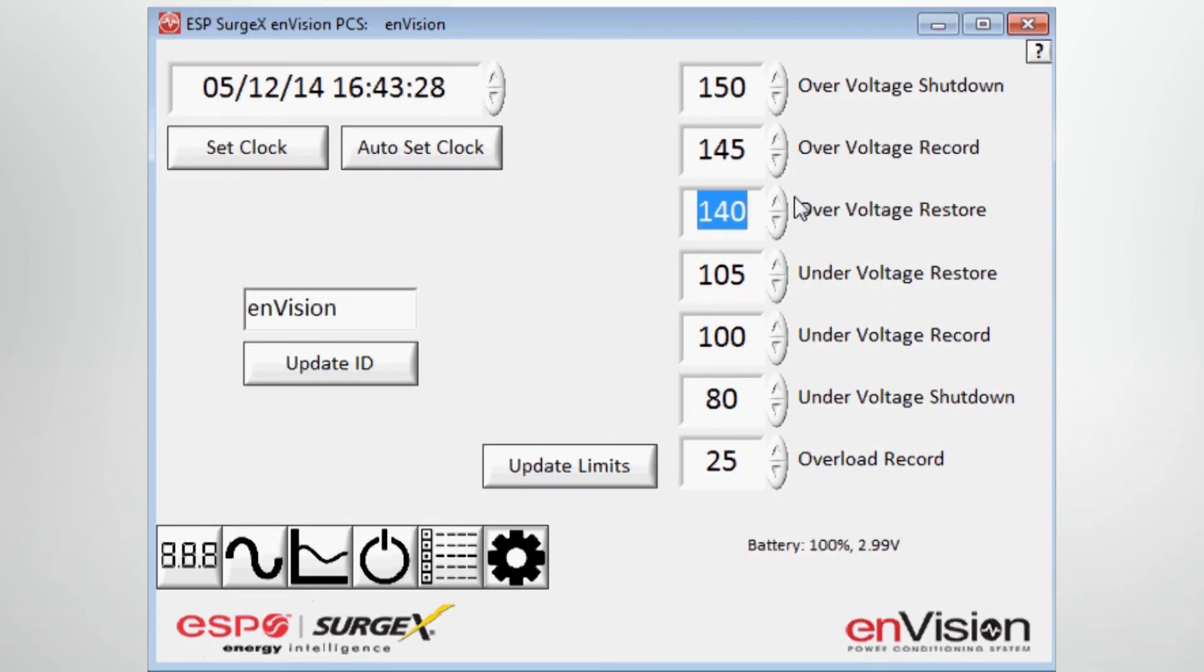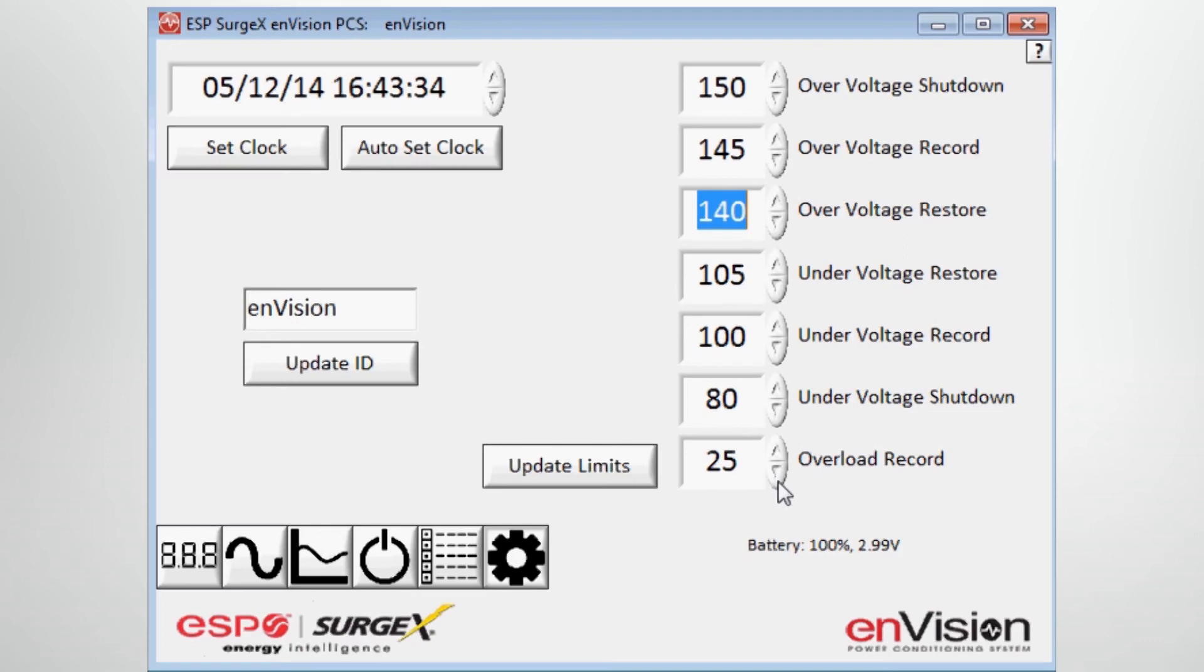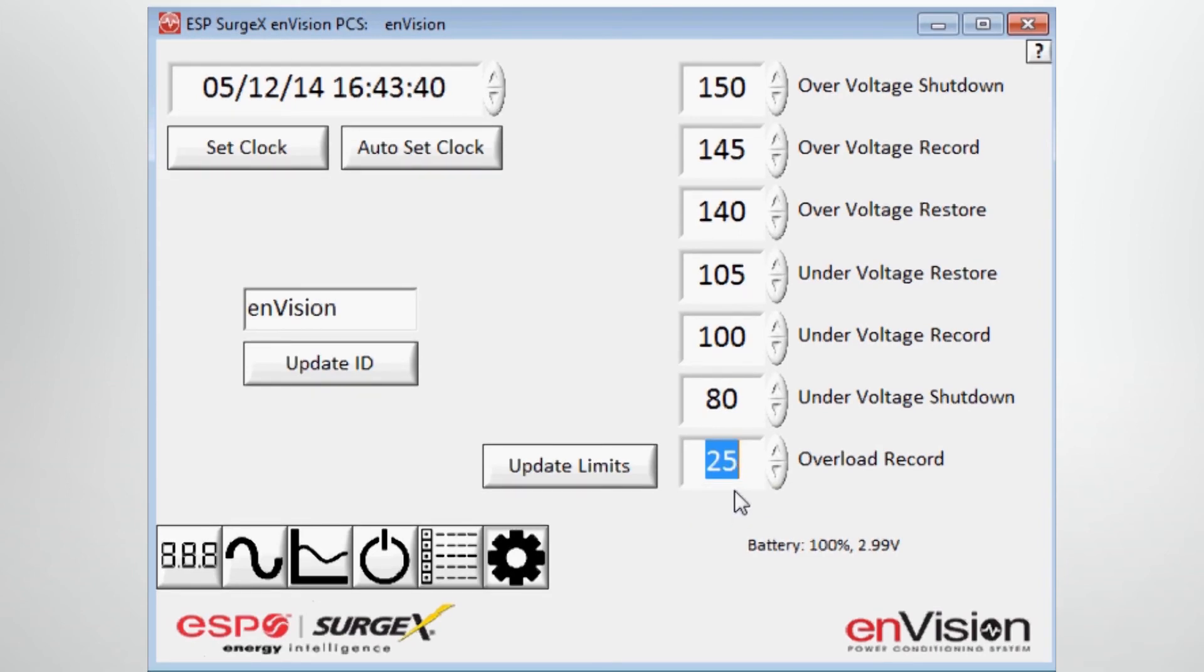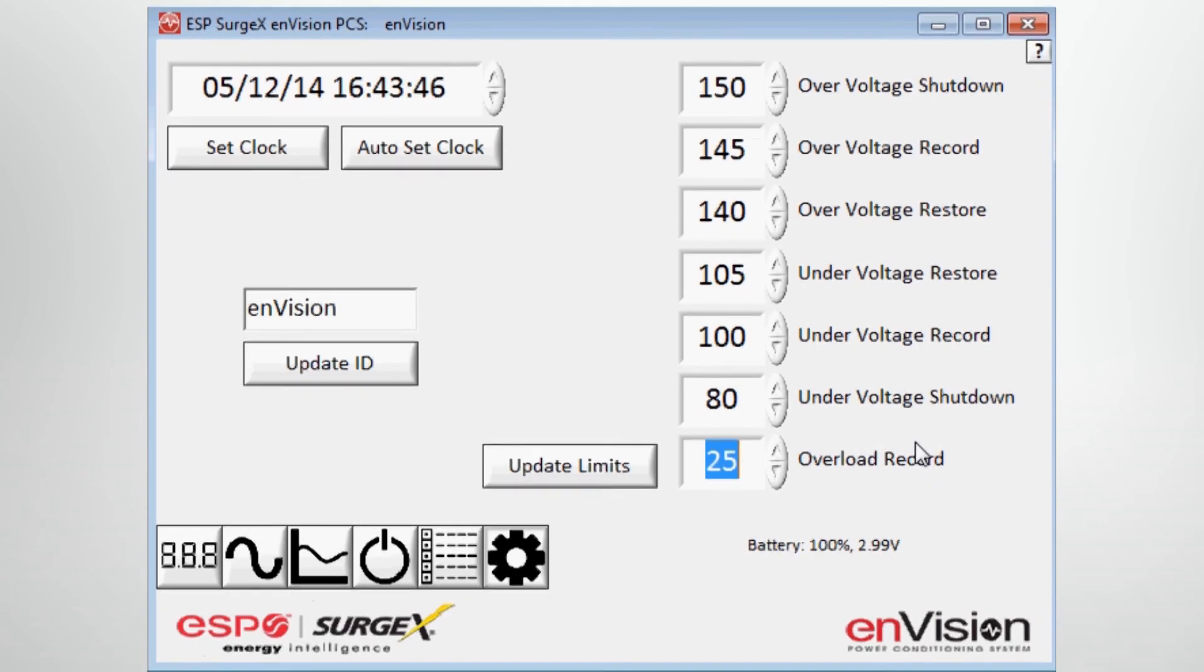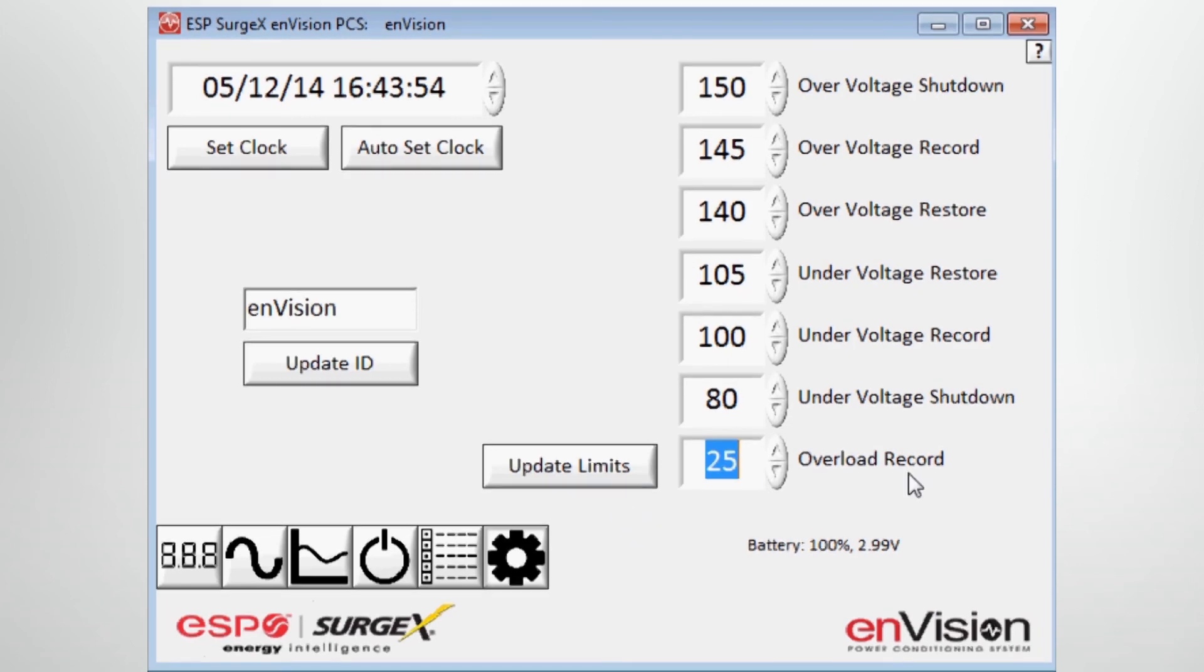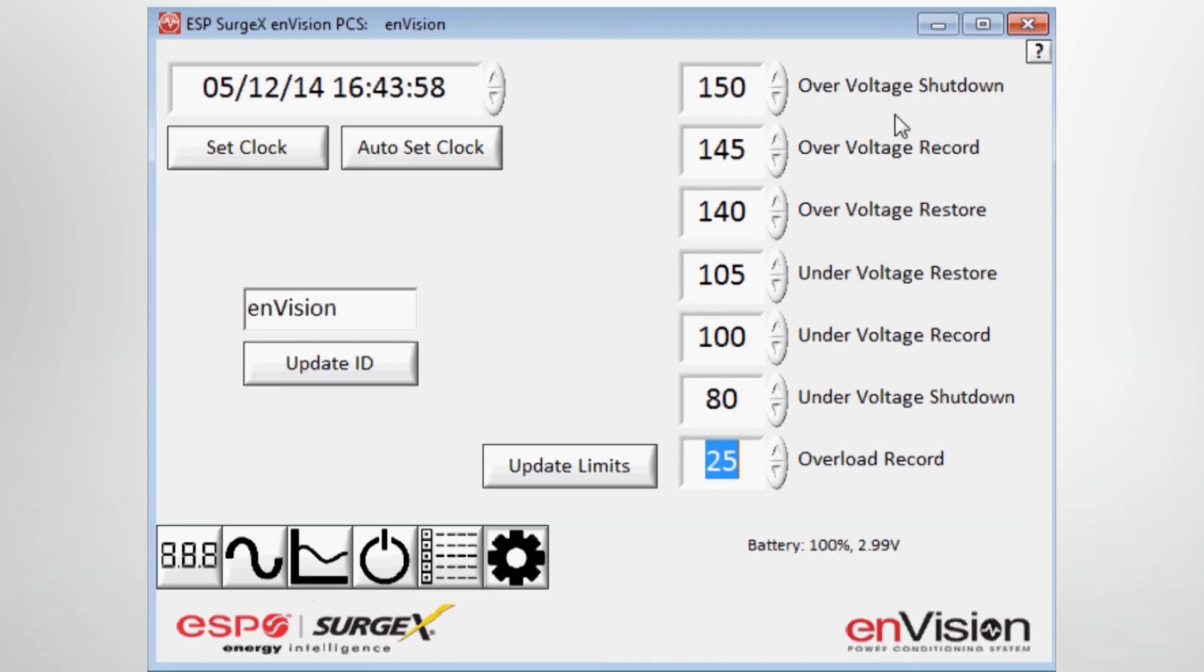And then lastly, you have the ability to record overload events. So this is an amperage setting. So if my overload current reaches 25 amps, I'm going to trip a record point that you will see in the historical data. And I can change that in one amp intervals. And that can be correlated to events that might have occurred. So it gives you the flexibility to look at that in addition to the voltage threshold levels.